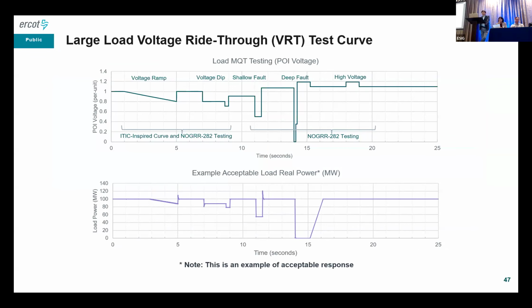This is the ERCOT recommended large load voltage ride-through test curve. It is essentially designed to test the performance of the large computational load that needs to meet the criteria in NOGRR 282, but also to check and understand the ride-through characteristics of other larger loads that are not required to meet the performance requirements in NOGRR 282. It starts with a flat start, and then goes down to a voltage ramp down test, which applies gradual, moderate voltage variations before initiating a sudden voltage dip, like a shallow fault, which is followed by a high voltage condition.